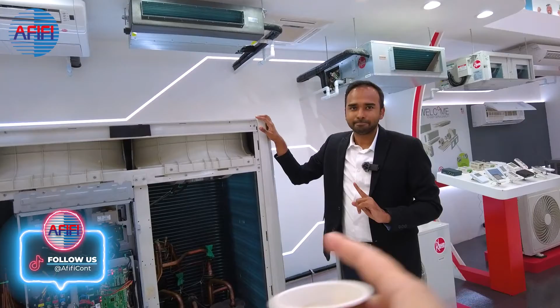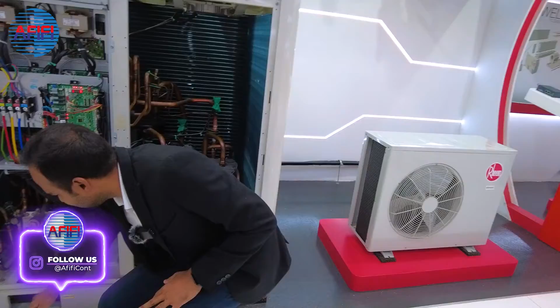The connection ratio, the capacity of indoor units divided by the capacity of the outdoor unit, is standard at 130%. You can also go to 200% if it's not a comfort cooling application, like a warehouse or storage. For comfort cooling, it's around 100%. If you send that to Laith, he will never design it for 200% for a villa or an office. If it's a warehouse, maybe you can optimize it. And then the pipe, you can take out from all four sides. Now I've taken it from the back, but you can take it from the front, left, right, or back.